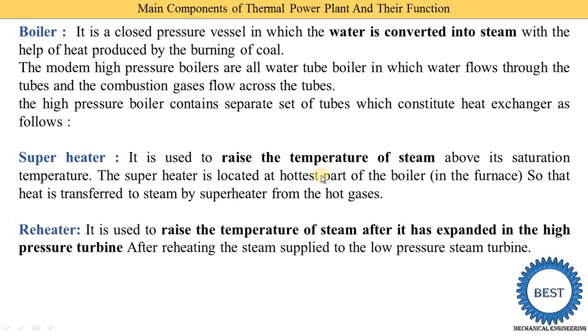The reheater is used to raise the temperature of steam after its expansion in the high-pressure turbine. After reheating, the steam is supplied to the low-pressure steam turbine. In a steam turbine there are three regions: high pressure, intermediate pressure, and low pressure. After the high-pressure region, we reheat the steam again — that's why it is called the reheater — and then it is supplied to the low-pressure or intermediate-pressure steam turbines.